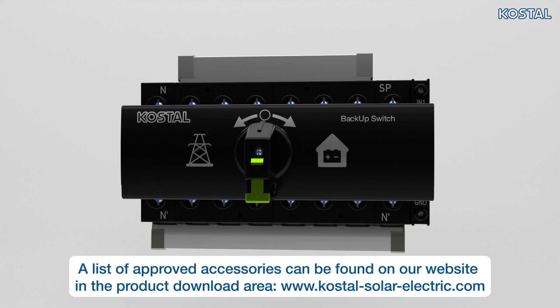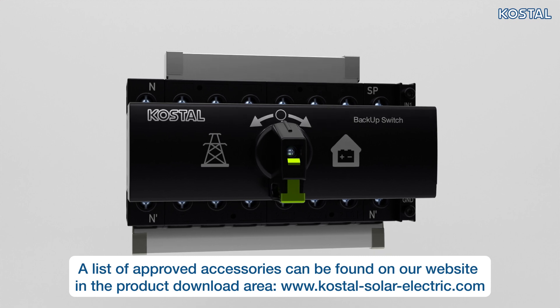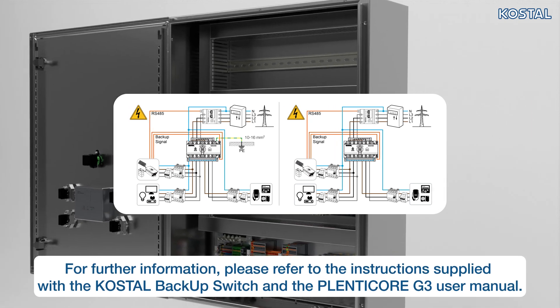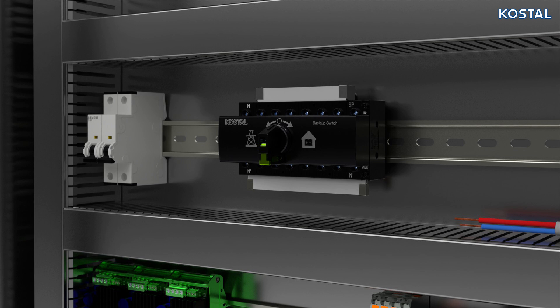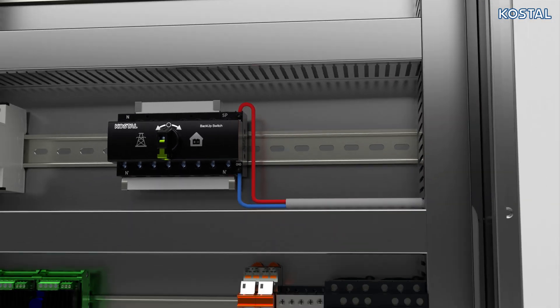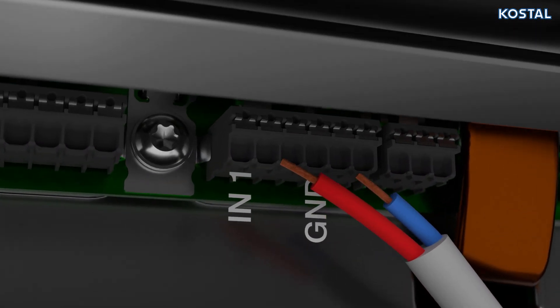If you have connected a battery to the inverter, it is possible to supply the house grid with energy via PV and battery in the event of a grid failure. This requires a Kostal energy meter and the Kostal backup switch or another backup box approved by Kostal. Fit the Kostal backup switch in the control cabinet or power distributor. When connecting, note which connection variant the energy provider specifies. Connect the signal line on the Kostal backup switch to the IN1 and GND terminals, then route and connect the signal cable to the X402 terminal.